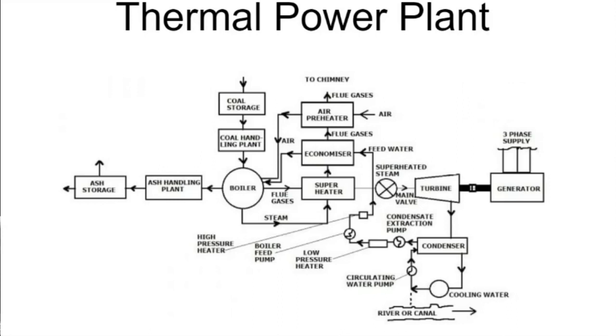Before going to the schematic diagram, let's discuss three more important disadvantages. First, the starting time required is very high — if you shut down the thermal power plant and want to restart it, it doesn't start like a fan with a button press. It takes a minimum of 6 to 8 hours in cold condition to restart.